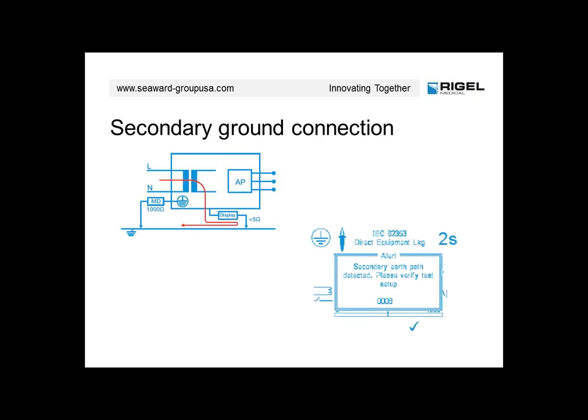So if that's the case, your safety tester will pop up with a screen giving you an alert that there is a secondary earth path, and you can disconnect the monitors or search for where the path is, remove it, and then do a successful test on the device itself.